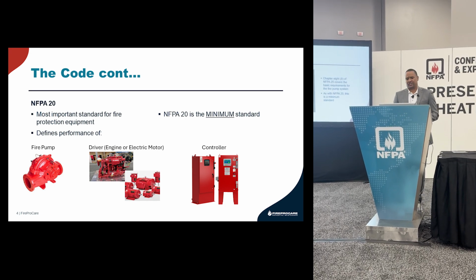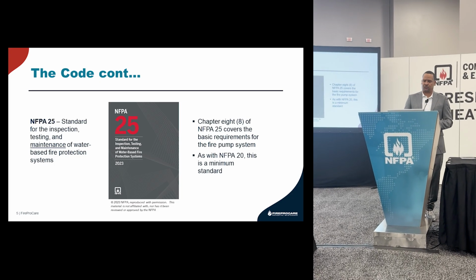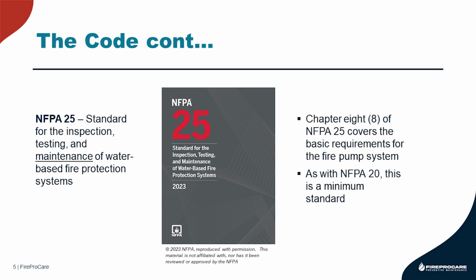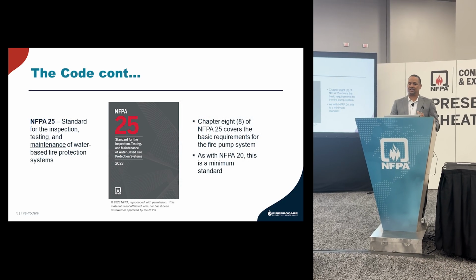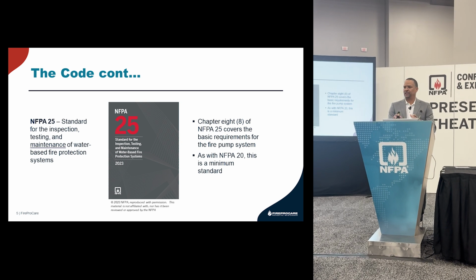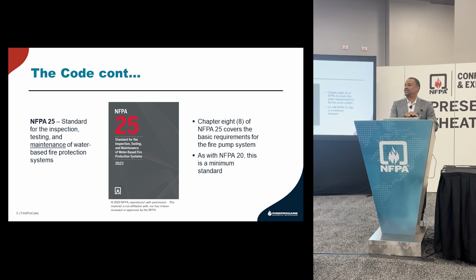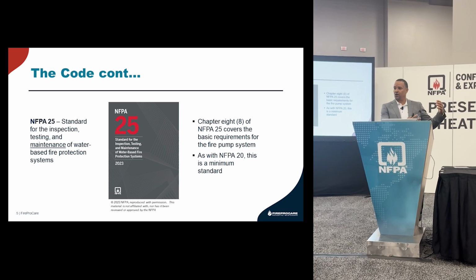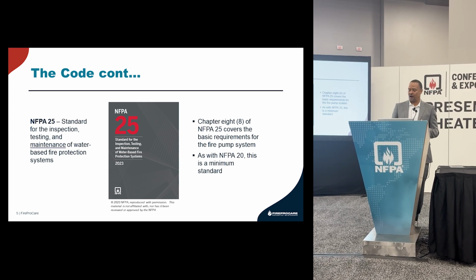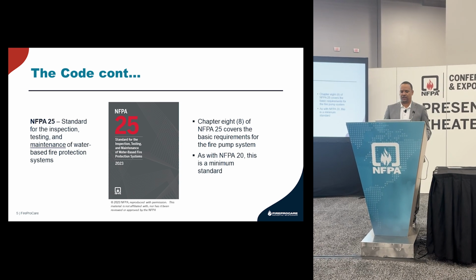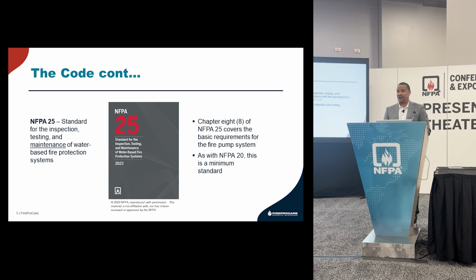As stated on the previous slide, NFPA 25 is also one of those standards. It defines the inspection, testing, and maintenance of the fire pump system. Chapter 8 covers what we do from a controller standpoint. As with NFPA 20, it's the minimum standard—I need you to remember that. It's not that you only have to do what's in NFPA 25; it's just the basic foundation. You could go above and beyond that if your locale requires it, but you have to start with that basic foundation: NFPA 25, Chapter 8.1.